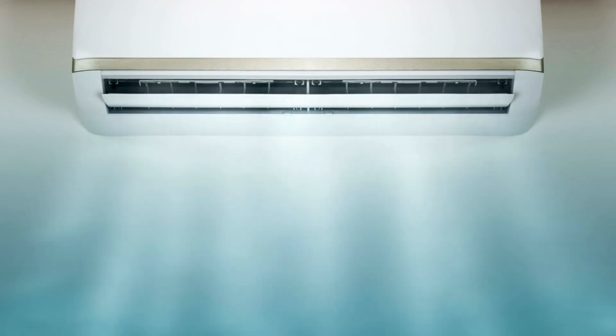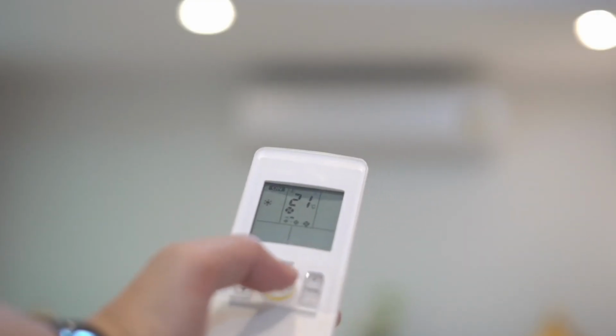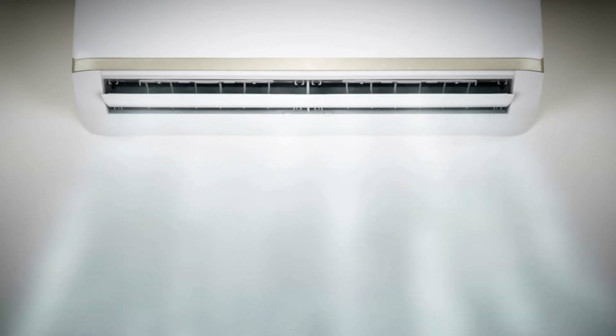Let's take an example. Imagine you're cooling a large room. You might have a 1-ton air conditioner capable of removing 12,000 BTUs per hour. Depending on the size and heat load of the room, this could lower the temperature by a few degrees, or maybe more. But if we tried to rate this in degrees centigrade, it wouldn't account for factors like heat from the sun, electrical appliances, or the number of people in the room.